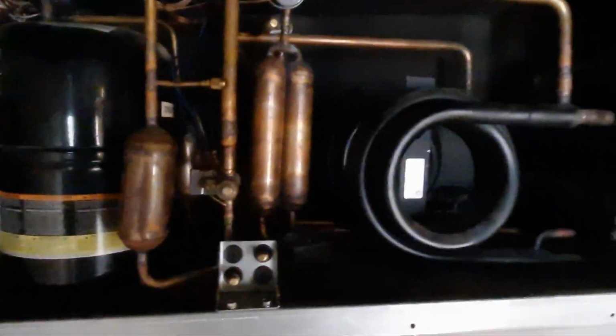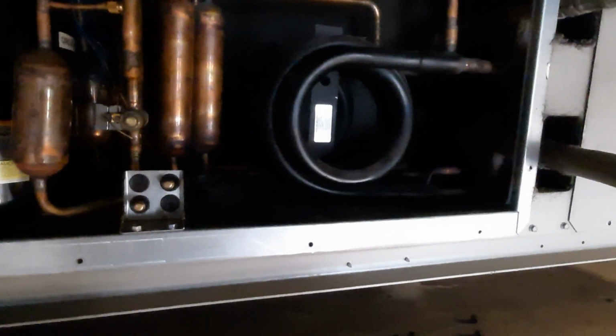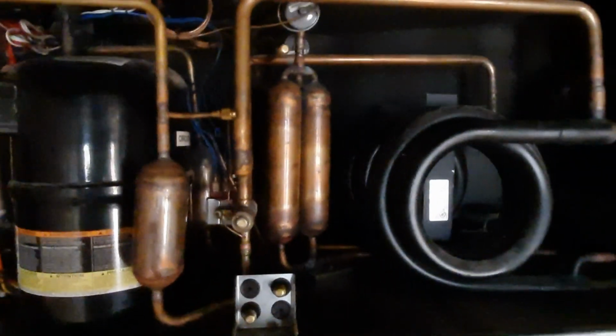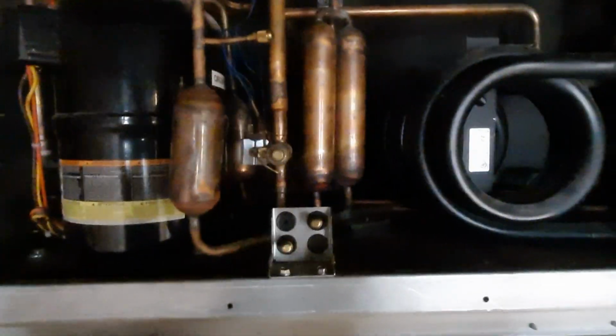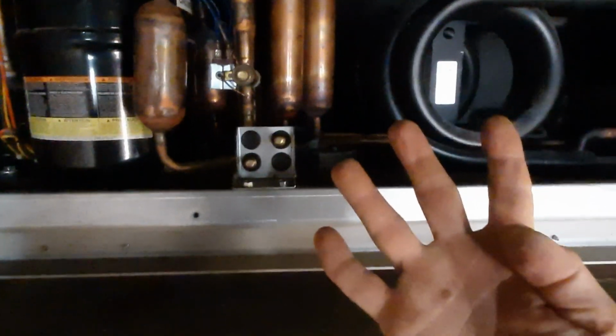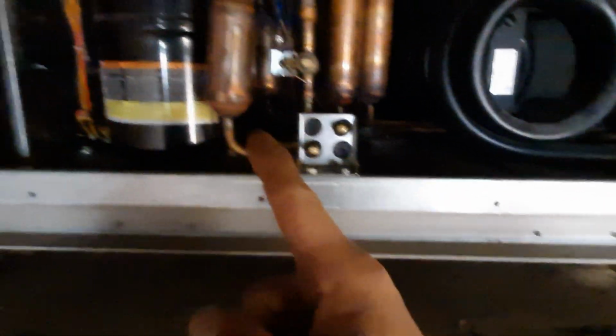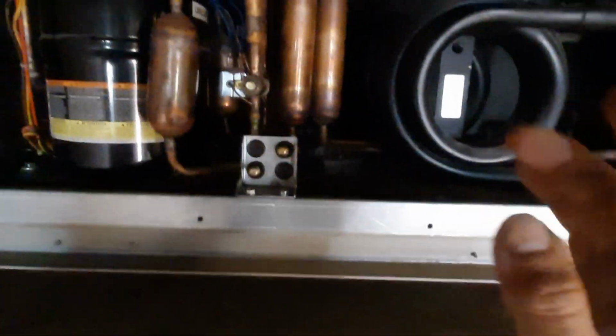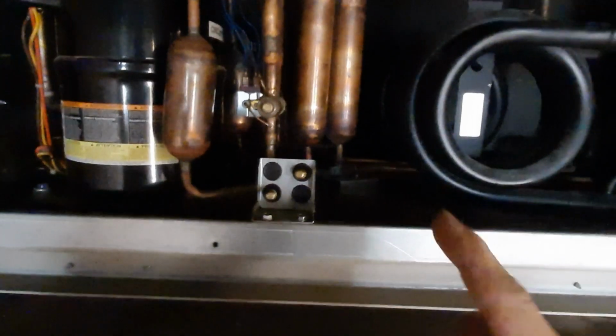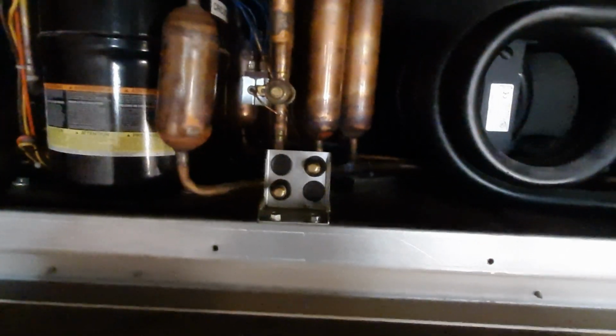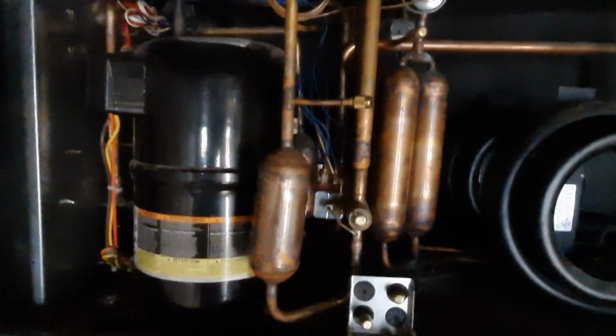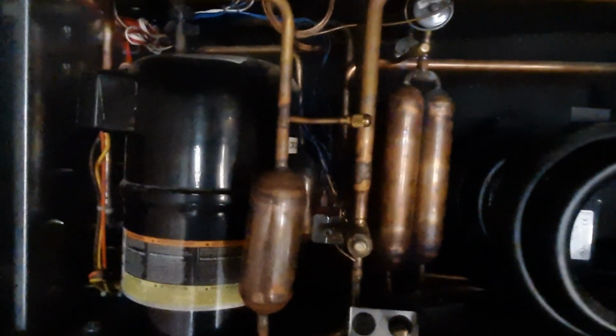I see a lot of guys, especially new guys to the trade, get tripped up when they see water source heat pumps. There's nothing real special about a water source heat pump. It's just the medium that we use to condense our refrigerant or evaporate our refrigerant, because we're a water source heat pump, and a heat pump reverses the refrigeration cycle. All refrigeration units have four major components: compressor, condenser, evaporator, and expansion device. Every system out there, doesn't matter what it is, freezer, cooler, chiller, all the same. The heat pump cycle's the same.